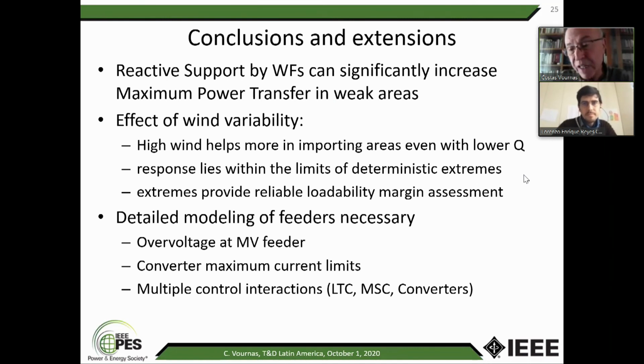Now, depending on the control, if it was just doing voltage control, it would increase the reactive power. So it would somehow help the system. And of course, in the case of the emergency, they are doing something more because they go also to their own limit. So the effect of the contingency on the wind farm is not important because it's not a contingency like a short circuit that can cause disruption of the wind farm. If we had a short circuit, it's a totally different story. I'm not covering it at all in this presentation, but we all know we have this low voltage ride-through, so they would respond according to the low voltage ride-through. But now the voltage in the feeder is always very close to nominal, so there is no such case where the wind farms can be part of the problem.